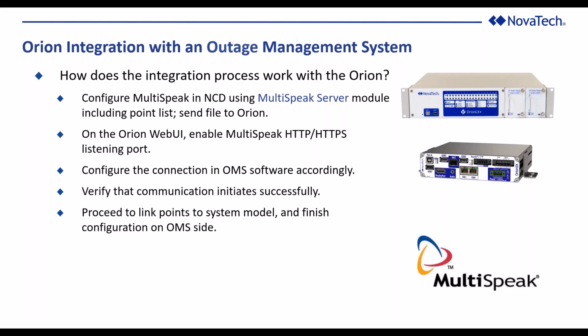You'll want to verify that the communication initiates successfully. You can view the comms in the web UI, and Jamie will show that too. Once that's all confirmed, once we have two-way communication, you can proceed to link points into the system model, and then finish configuration on the OMS side.